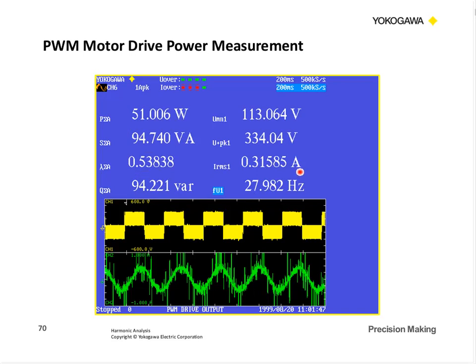And look at the peak and the RMS value. And here's where we use the mean value. This mean value could be the fundamental voltage, and that's why I brought that up earlier, because this mean value is quite important a lot of times in our drive work as the fundamental, and that's what really relates to the torque of the motor.